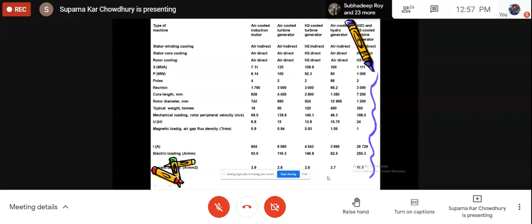Current density: you can see that for this one, the current density allowed is very large. That is because the stator cooling is very effective here. We have direct water cooling for the stator, so we can go for a higher current density, because whatever current density we allow for the machine is related to the cooling. If the cooling is effective, ultimately what is important is the temperature rise. Now, you need not just mug up this table. This is just for example. I am just showing it as an example.